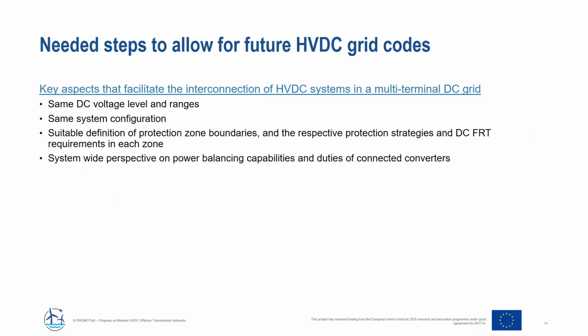Having in mind the broad design possibilities for future HVDC grids and the just discussed challenges with regard to designing an HVDC grid code, there are still several steps needed to allow for future HVDC grid codes. In general, key aspects that facilitate the interconnection of HVDC systems in a multi-terminal DC grid are same DC voltage levels and ranges, and having the same system configuration. With regard to the protection, a suitable definition of protection zone boundaries and the respective protection strategies and DC fault ride-through requirements in each zone need to be defined.